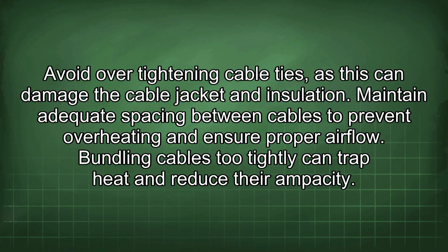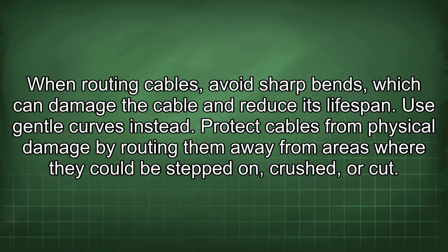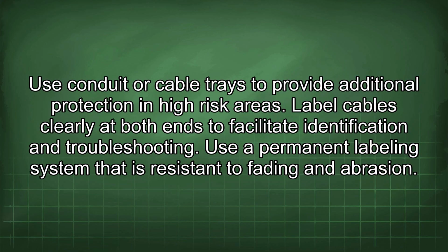Maintain adequate spacing between cables to prevent overheating and ensure proper airflow. Bundling cables too tightly can trap heat and reduce their ampacity. When routing cables, avoid sharp bends, which can damage the cable and reduce its lifespan. Use gentle curves instead. Protect cables from physical damage by routing them away from areas where they could be stepped on, crushed, or cut. Use conduit or cable trays to provide additional protection in high-risk areas.